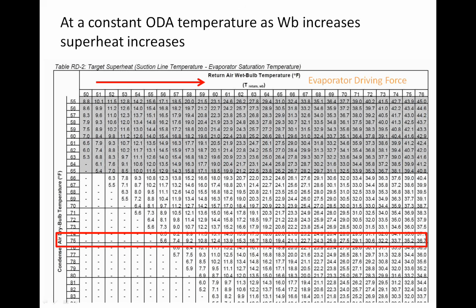Well, you can see as the return air wet bulb temperature goes up, our target superheat also goes up, right? So the load, the heat and humidity, also has an impact on the performance of a fixed orifice system. These are relationships we have to make sure we understand, because on a fixed orifice system we have to measure outdoor air temperature and return air wet bulb accurately to determine the target superheat. If any of those load conditions change, our target's going to change.